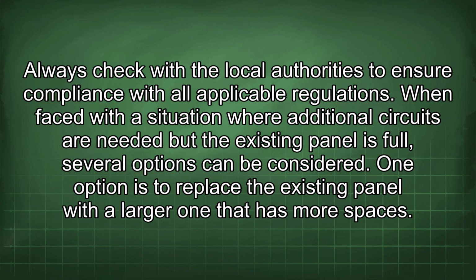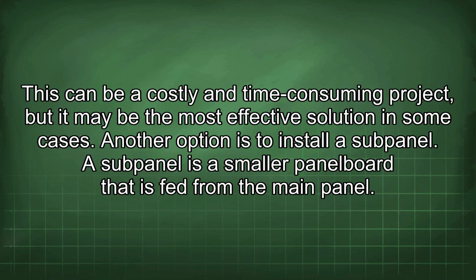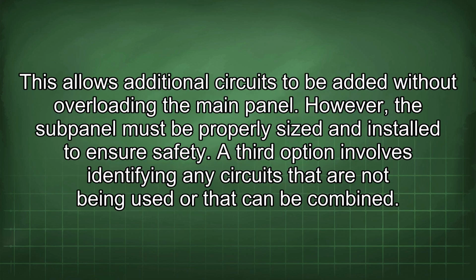When faced with a situation where additional circuits are needed but the existing panel is full, several options can be considered. One option is to replace the existing panel with a larger one that has more spaces. This can be a costly and time-consuming project, but it may be the most effective solution in some cases. Another option is to install a subpanel. A subpanel is a smaller panel board that is fed from the main panel. This allows additional circuits to be added without overloading the main panel. However, the subpanel must be properly sized and installed to ensure safety.